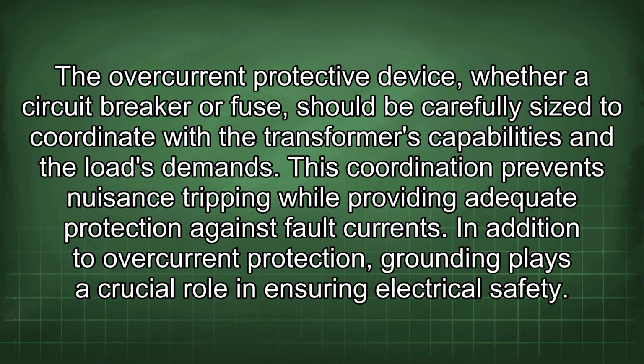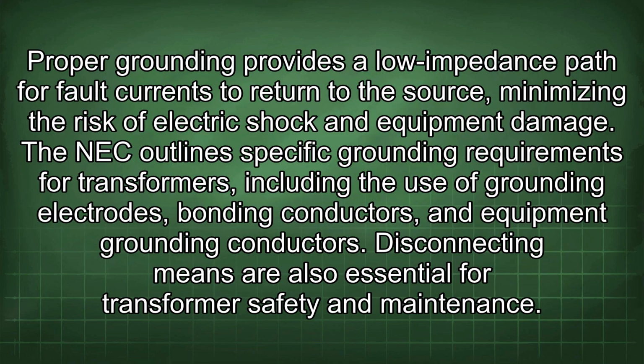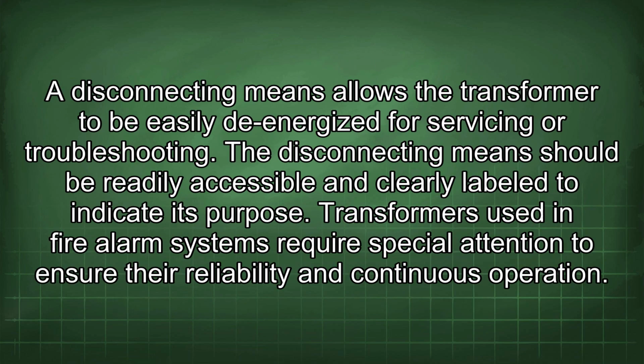In addition to overcurrent protection, grounding plays a crucial role in ensuring electrical safety. Proper grounding provides a low impedance path for fault currents to return to the source, minimizing the risk of electric shock and equipment damage. The NEC outlines specific grounding requirements for transformers, including the use of grounding electrodes, bonding conductors, and equipment grounding conductors. Disconnecting means are also essential for transformer safety and maintenance. A disconnecting means allows the transformer to be easily de-energized for servicing or troubleshooting. The disconnecting means should be readily accessible and clearly labeled to indicate its purpose.